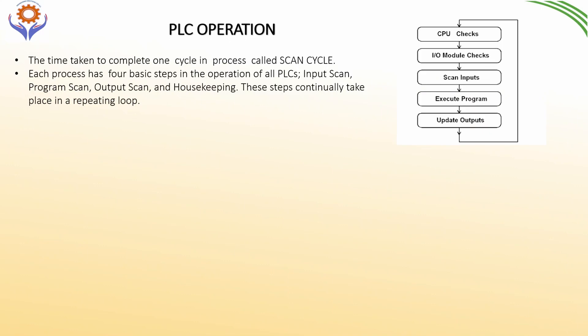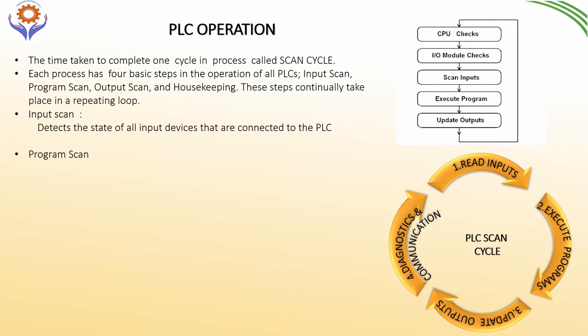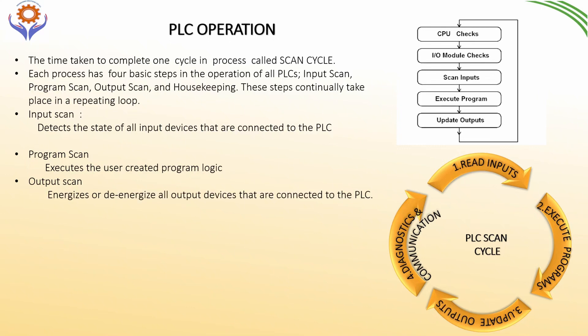First of all, what is input scan? Input scan detects the state of all the input devices that are connected to the PLC. The second one is program scan — it executes the user-created program logic to control the system. The third one is output scan — it energizes or de-energizes all the output devices that are connected to the PLC.